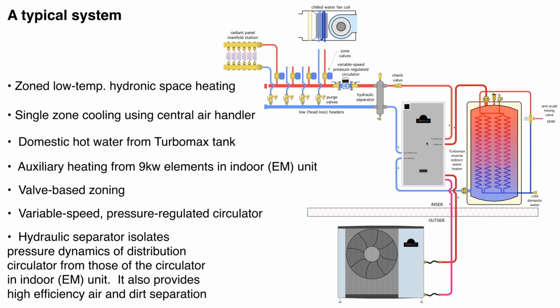I suppose this latest blast of cold air down through the Midwest and down into Texas can convince people it's good to have an auxiliary heating element anytime you have a heat pump, not only for abnormally cold temperatures, but as a backup. If there is any service that's done on the refrigeration system, you do have backup heating. And 9 kW converts to roughly 30,000 BTUs per hour. So it's a pretty significant amount of auxiliary heat capability. So as they say, that's a typical system, kind of what the concept of this heat pump was designed around.